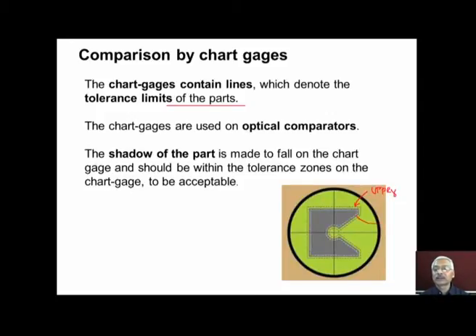And then we have another line inside corresponding to the lower limit of the workpiece. This is the shadow or image of the workpiece. The image is made to fall on the chart gauge, and if the shadow is within the tolerance zones, meaning the edges of the shadow are between the upper limit and lower limit, the workpiece is acceptable.